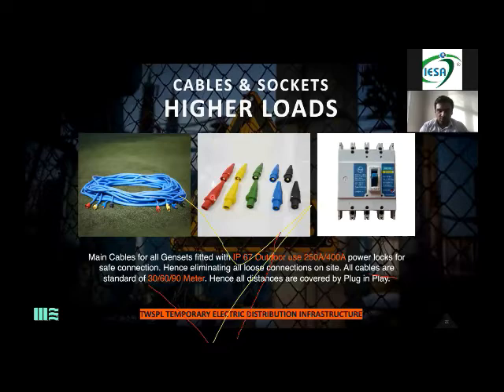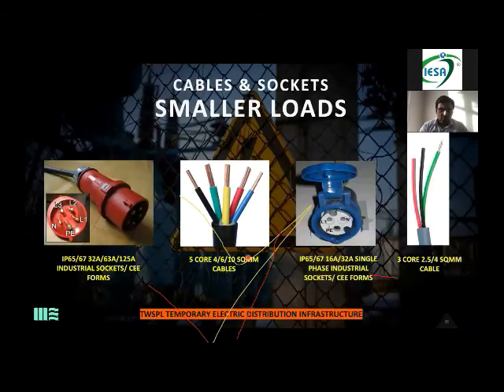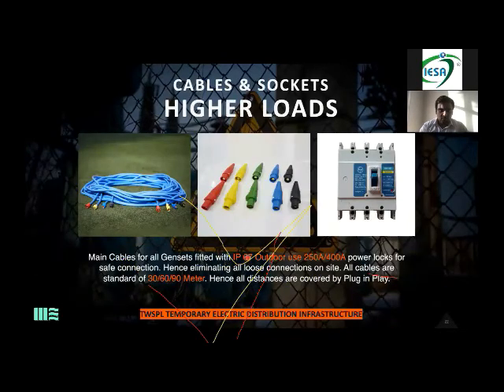So you are absolutely sure on site that no wrong connection will happen, because any loose connection can lead to a fire or a big accident on site. So all the homework needs to be done from the warehouse. All these power locks are IP67. I told you the sockets are 65 and 67. As soon as you use IP67, they are dust tight and absolutely watertight, because most of the time your main cables are outside.